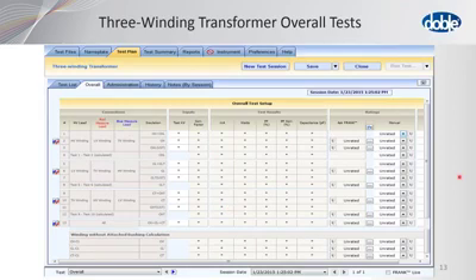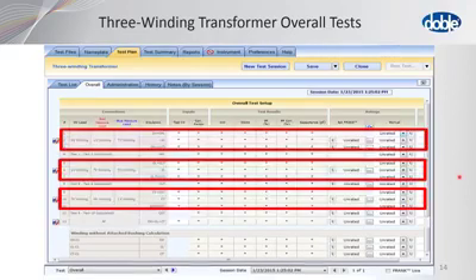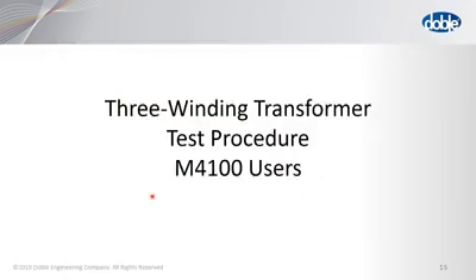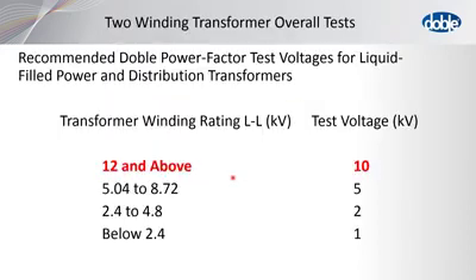And the thing that's nice about a 3-winding transformer test procedure is it's actually three 2-winding transformers that we do in series. The first one contains the high and the low voltage winding. The second one is the low and the tertiary, and the third one is the tertiary and high. And I'll go through this in a little more detail so you can understand. So here is the 3-winding transformer test procedure for the M4100 users.